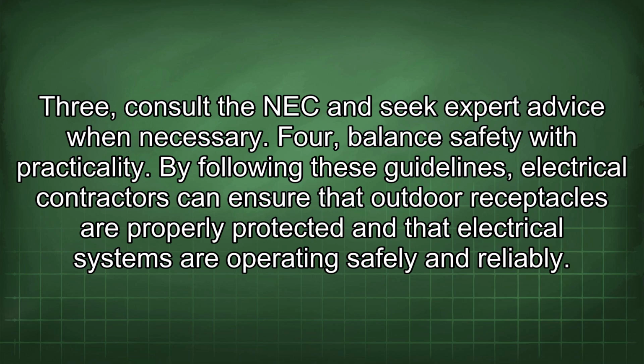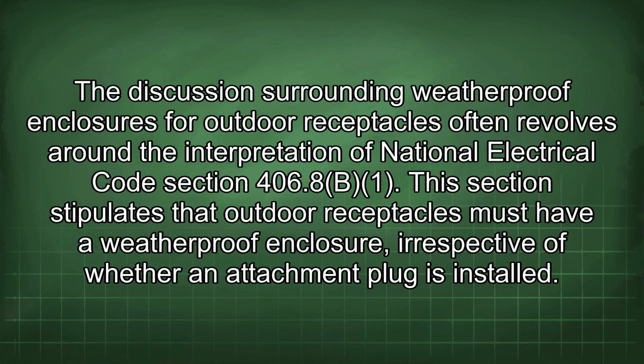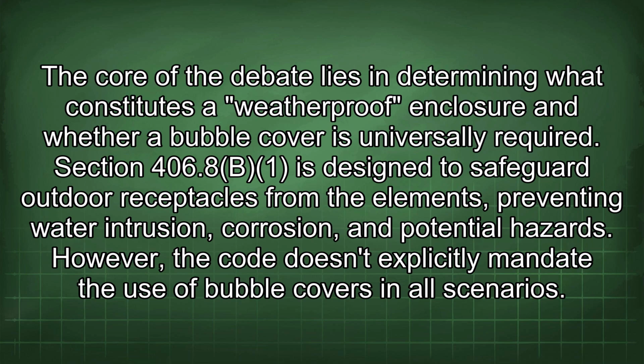The discussion surrounding weatherproof enclosures for outdoor receptacles often revolves around the interpretation of National Electrical Code Section 406.8(B)(1). This section stipulates that outdoor receptacles must have a weatherproof enclosure, irrespective of whether an attachment plug is installed. The core of the debate lies in determining what constitutes a weatherproof enclosure and whether a bubble cover is universally required. Section 406.8(B)(1) is designed to safeguard outdoor receptacles from the elements, preventing water intrusion, corrosion, and potential hazards. However, the code doesn't explicitly mandate the use of bubble covers in all scenarios.